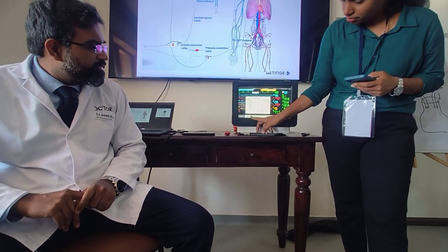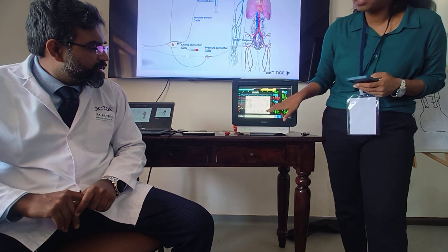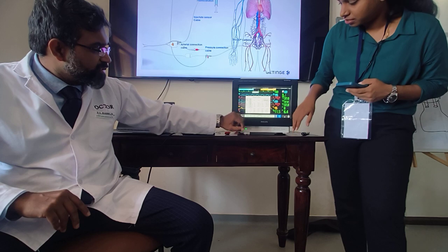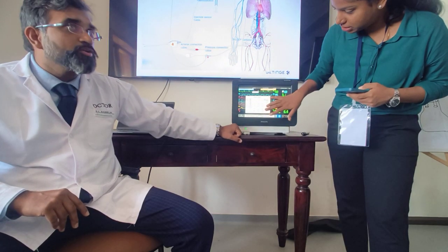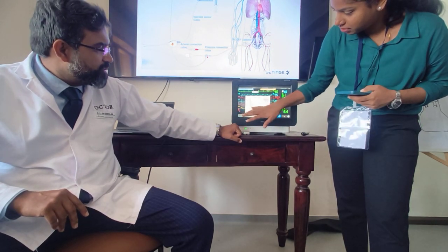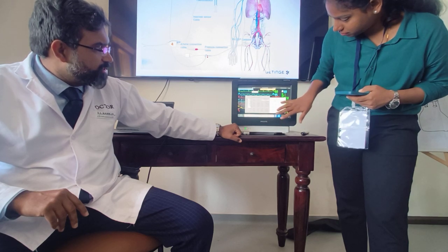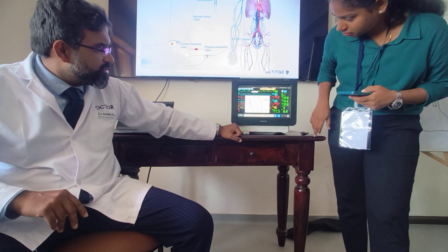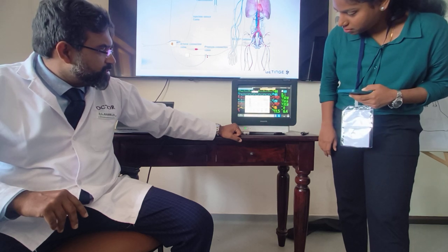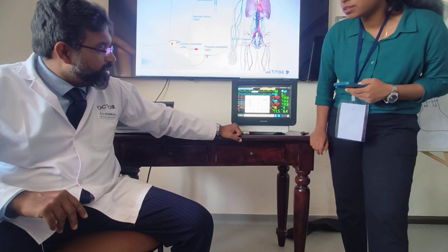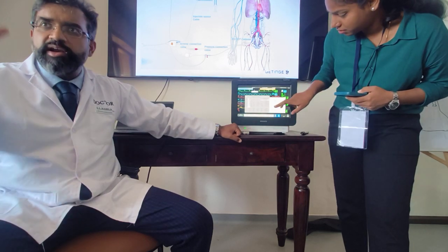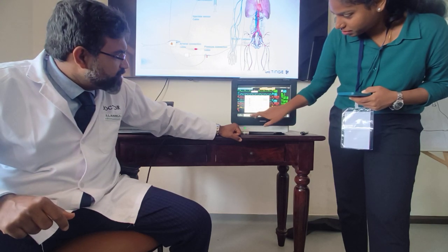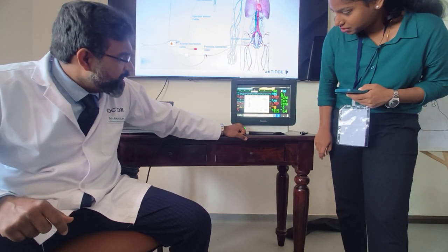Just go and perform the calculation and you'll get the values if they are not coming. So if you go to this and omit the CVP, make the CVP 0 here in the demo mode. In fact, let's see what happens. Make it 0 and perform calculation. Make it 200 maybe, make it 300. So CVP, let's make it 300, like it's blocked, the catheter is blocked. Okay, and let's see your calculation. Perform calculation. Is the SVR coming?